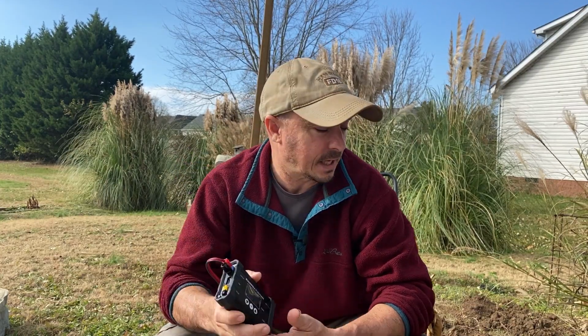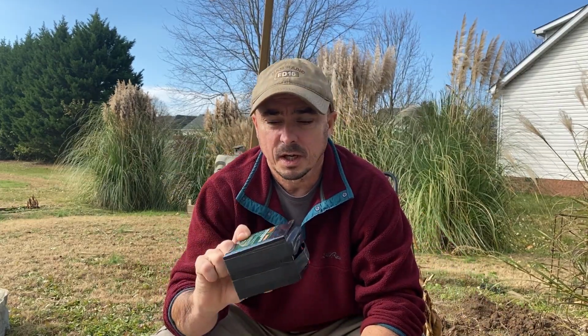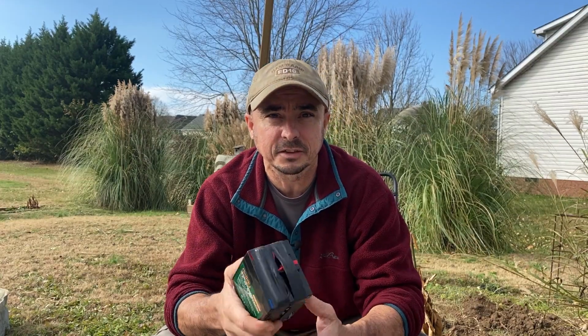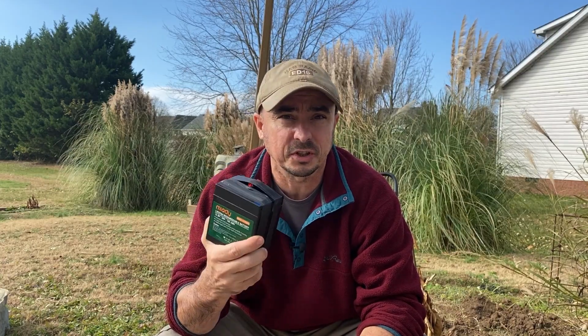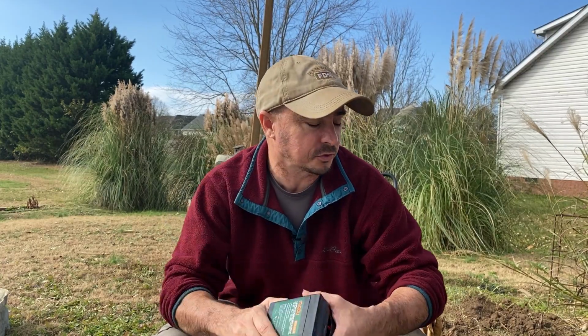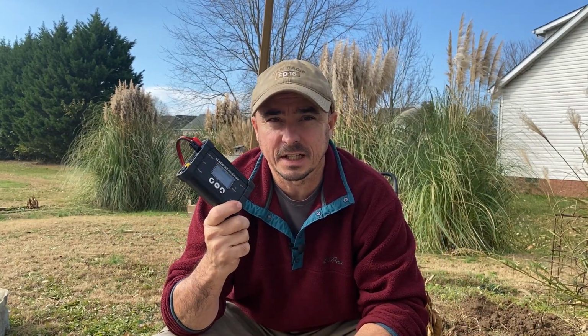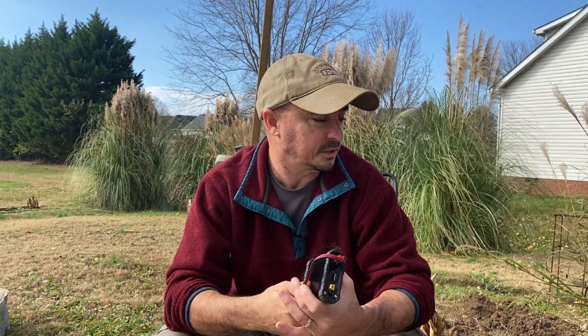So we can do that a couple of different ways. With the Power Mini and with a lot of other solar charge controllers, we can set a low voltage disconnect. So if we look at a spec sheet for a battery, let's assume its BMS is set to disconnect at 10.5 volts. If we simply take this device and set it to disconnect at 11, then the BMS never shuts off the batteries and we never run into this problem to begin with.